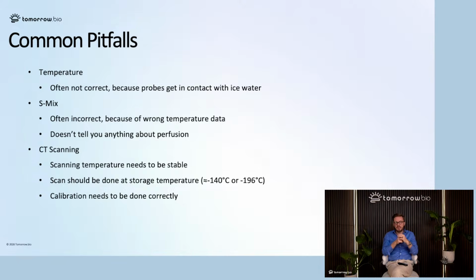If we see this in our cases, you will see either the graph is not there, and it says there was no meaningful data, it could not be collected, or the graph is there, and then on top of the report it says that this data should not be considered correct, and there might be significant mistakes. Exposure of the thermocouple, the temperature probe, to ice water is a very, very common mistake and problem, which also then leads to the S-Mix that I already briefly mentioned. If the temperature data is not correct, the S-Mix calculation is not correct, so it's not meaningful.